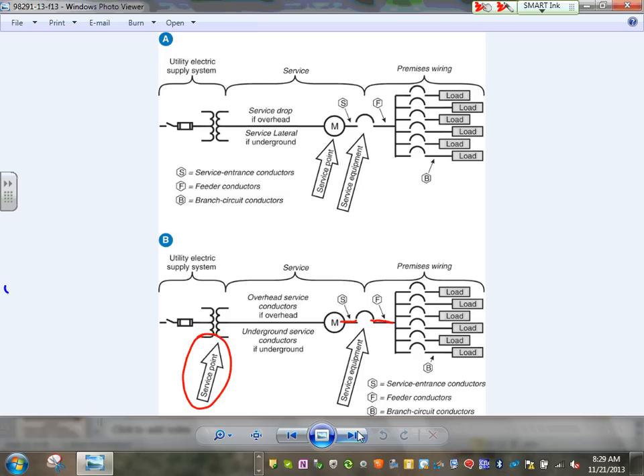There's service drop. These are the power conductors coming into the service point. From the service point into the building, that will be your service entrance conductors. Any comments, guys? Any questions? All you have to worry about, Adam, is just service entrance conductors coming from the transformer inside your building. You have to size them. In our project, guys, the service point will be the CT cabinet. That's where we pull the conductors into the CT cabinet, out of the CT cabinet into the transformer that will be owned and operated by the utilities.